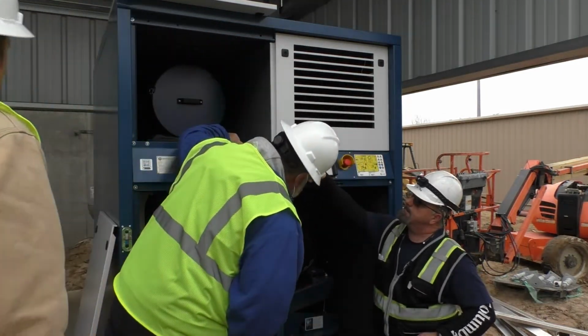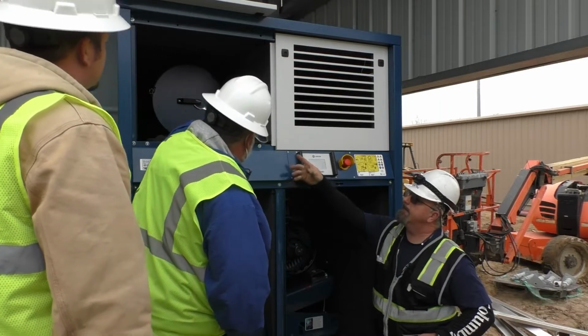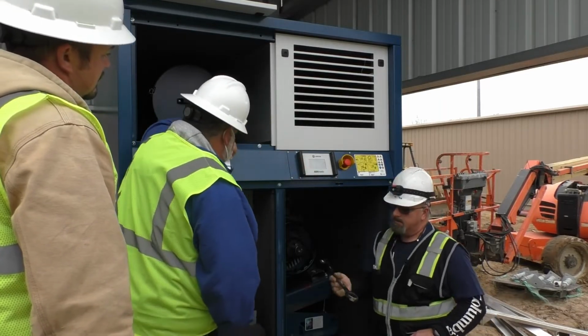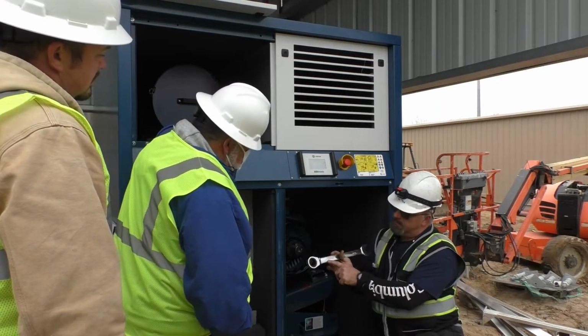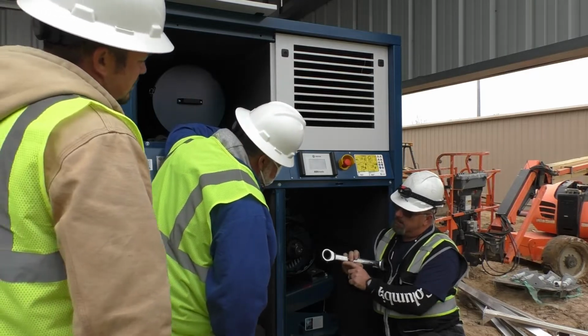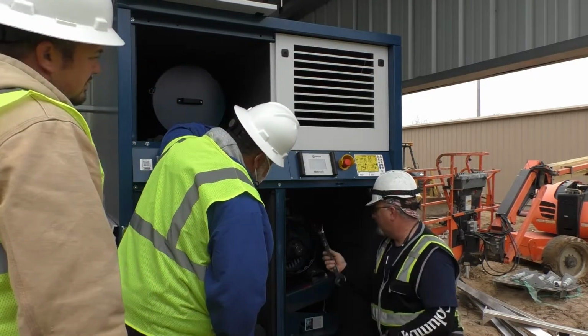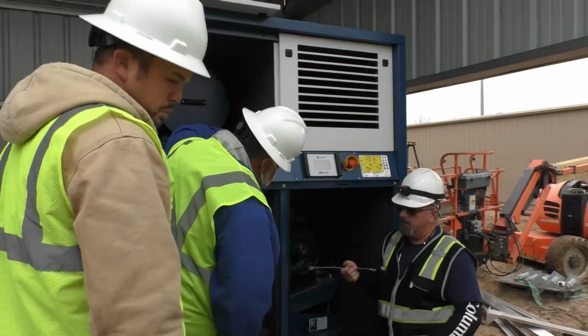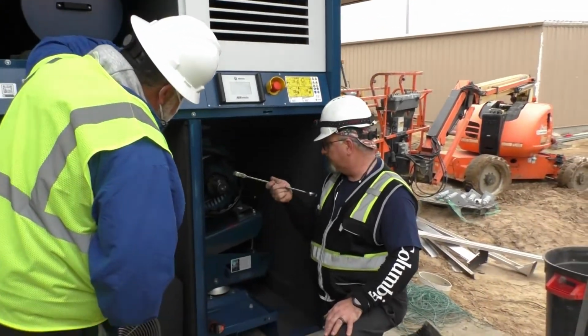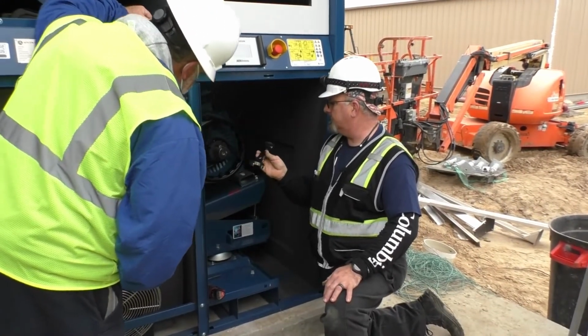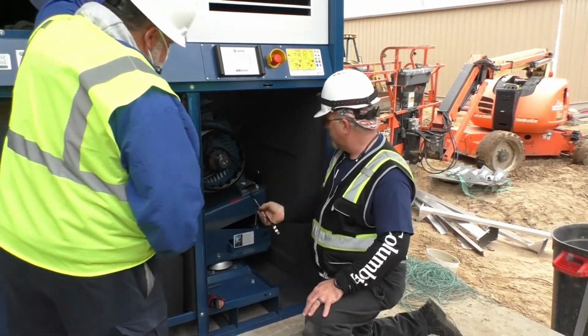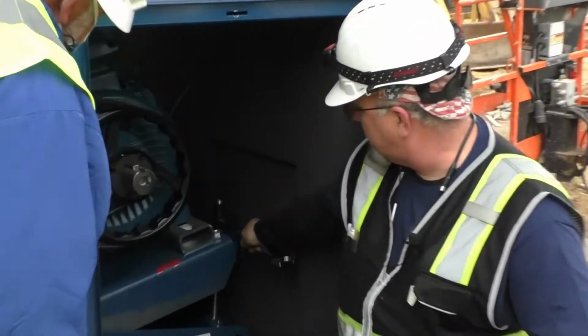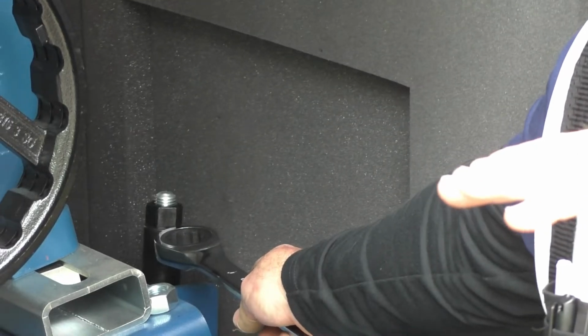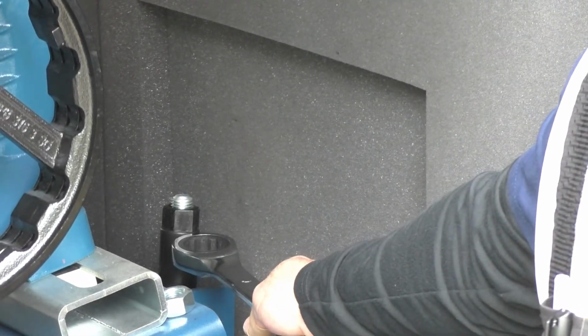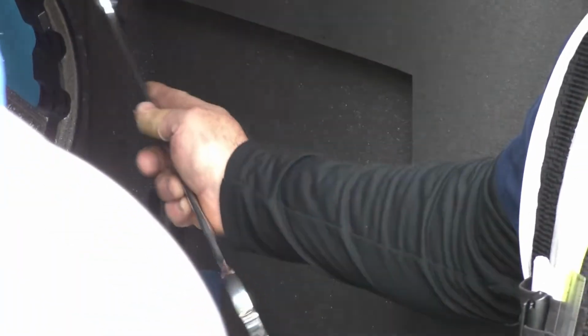There's a wrench right up there, if you will hand me that. Gear wrench? Yep. So basically a ratchet wrench, it gives you an indicator of which way you're turning. So to raise it up, you want to loosen, and to lower it, you would tighten. So basically what you're doing is this black piece right here, you're raising it up to raise the motor, you're lowering it down to allow the motor to take the tension.